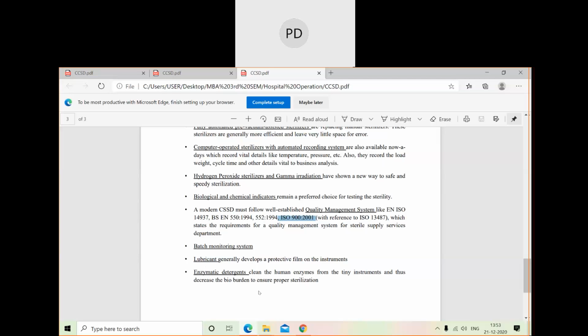And enzymatic detergents clean the human enzymes from the tiny instruments and thus decrease the bioburden to ensure proper sterilization. Enzymatic detergent is used, for example, for OT instruments. We use those trays for cutting patients' skin or some areas. In those instruments this enzymatic detergent is very much needed because that only can wash away human enzymes. That is the reason for OT instruments we are using enzymatic detergent.